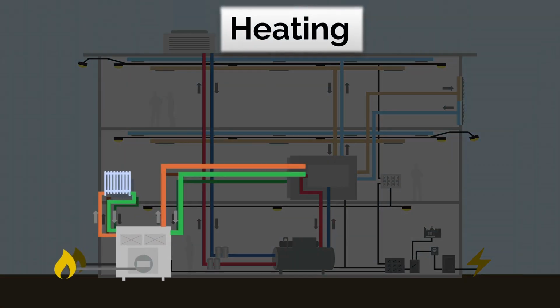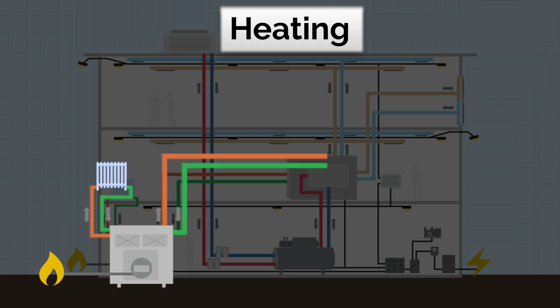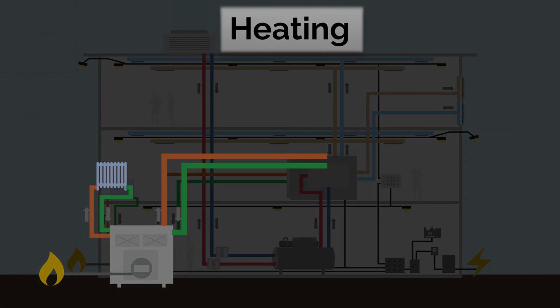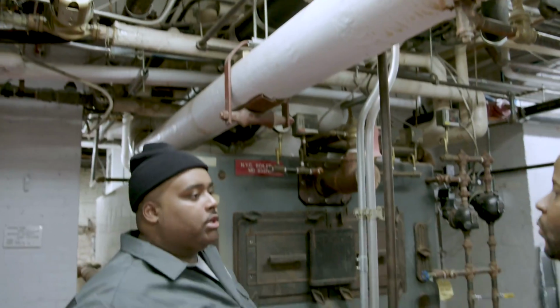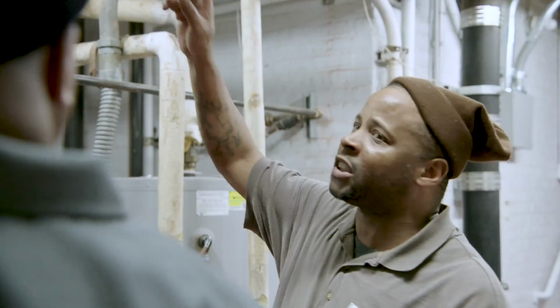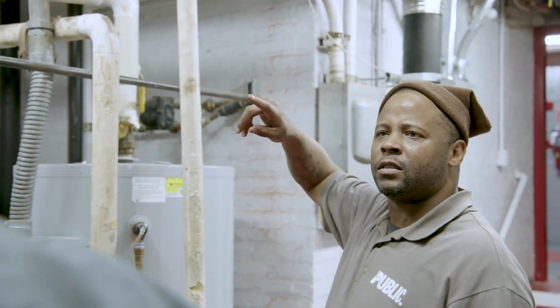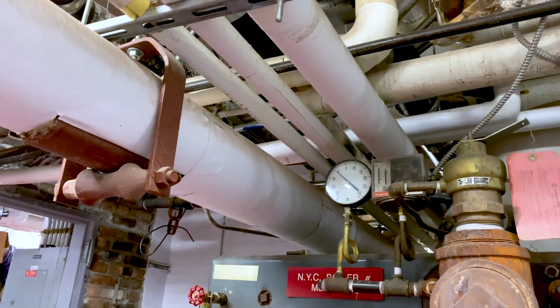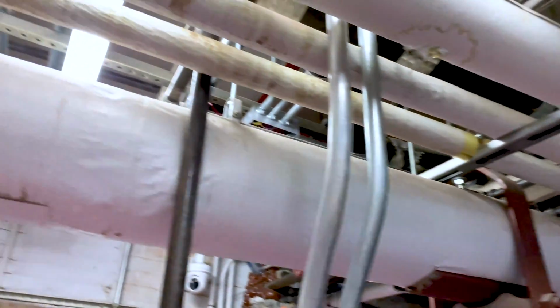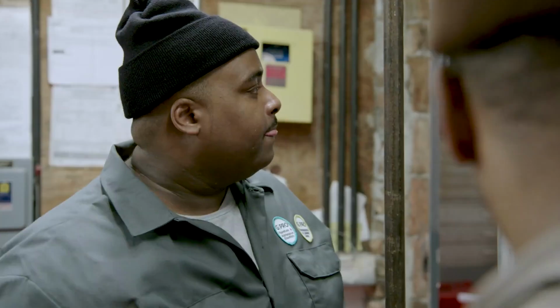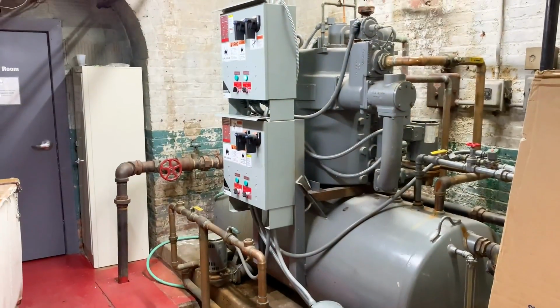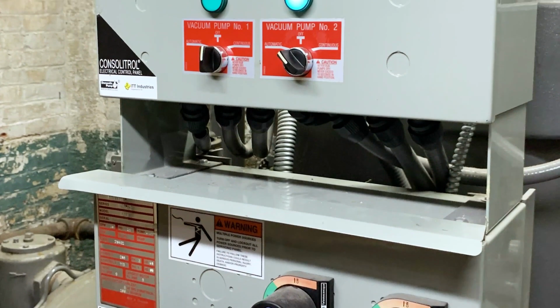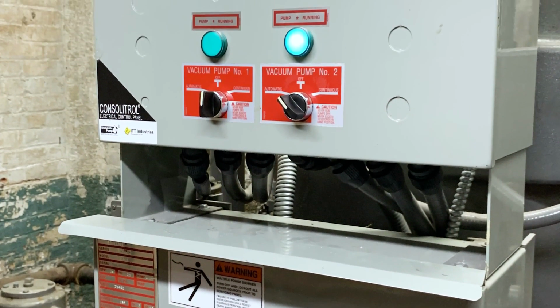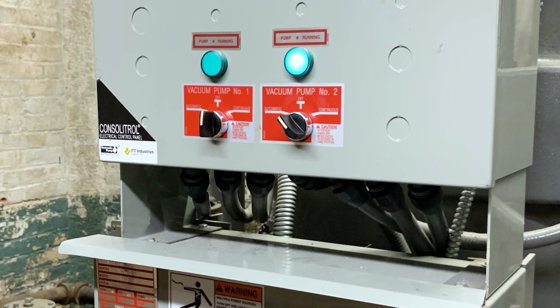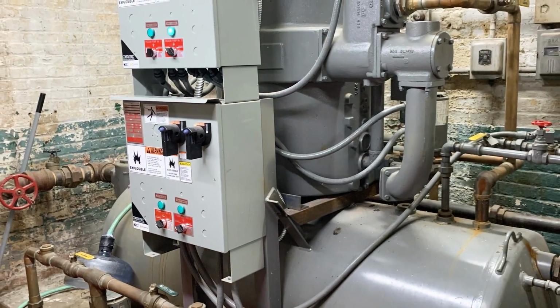Steam is delivered by piping to terminal units such as radiators or heating coils to transfer heat. In the boiler room, we also see supply piping and return piping. These circulate the steam to the terminal units and carry the condensed steam, which is water, back to the boiler to be heated again. The condensate receiver collects that water, which is important for efficient boiler operations. Ours uses a vacuum system. Others use pumps or just gravity to collect the condensate.